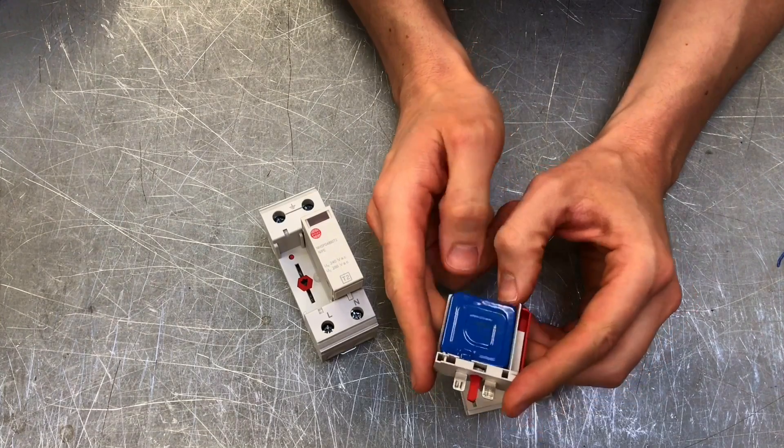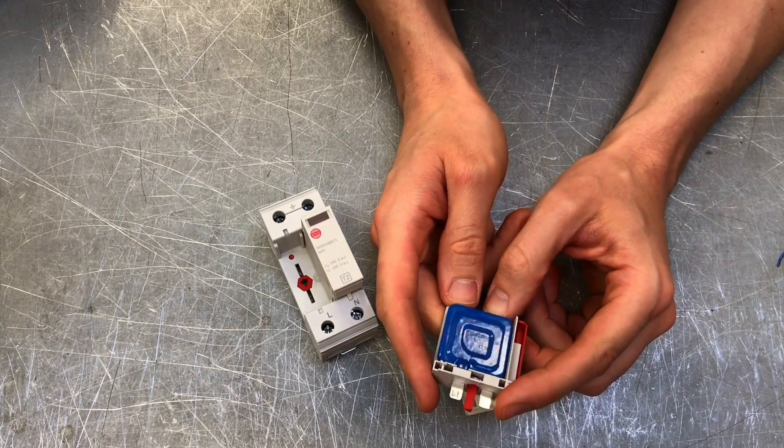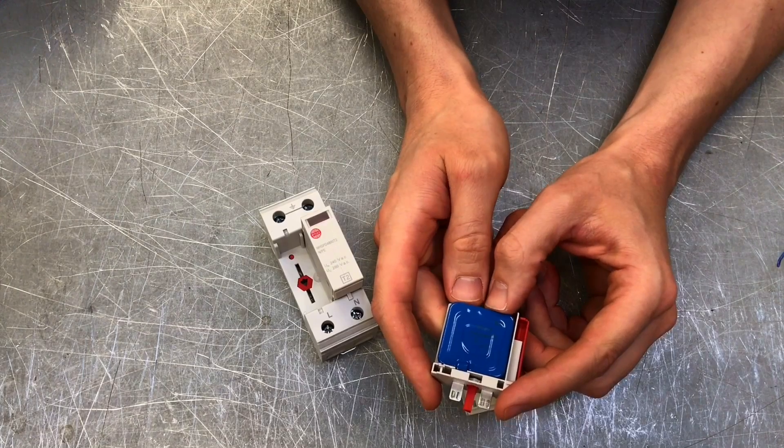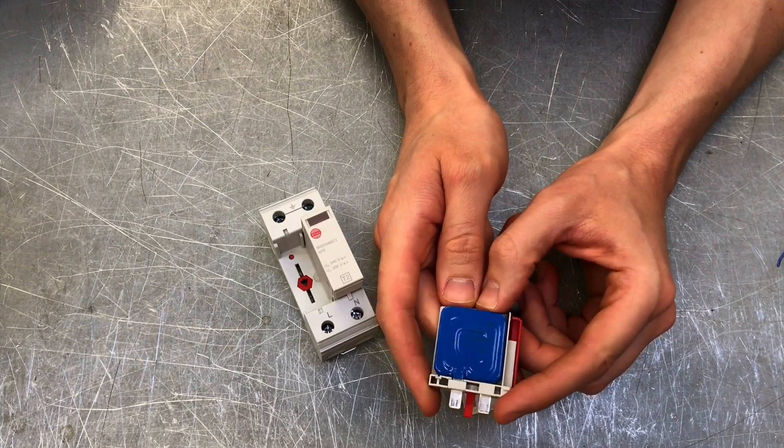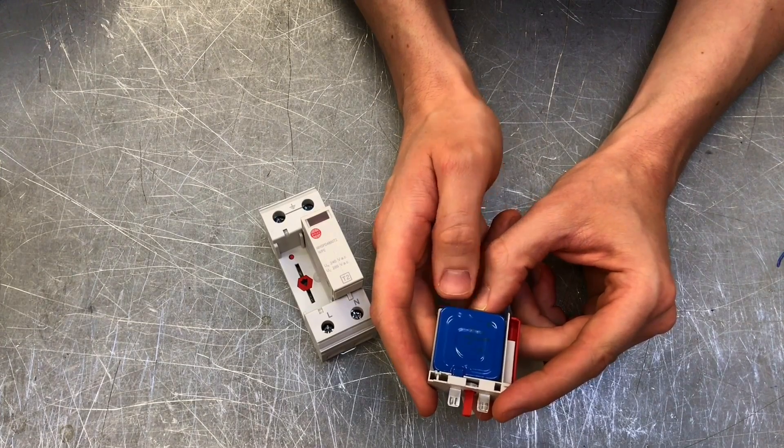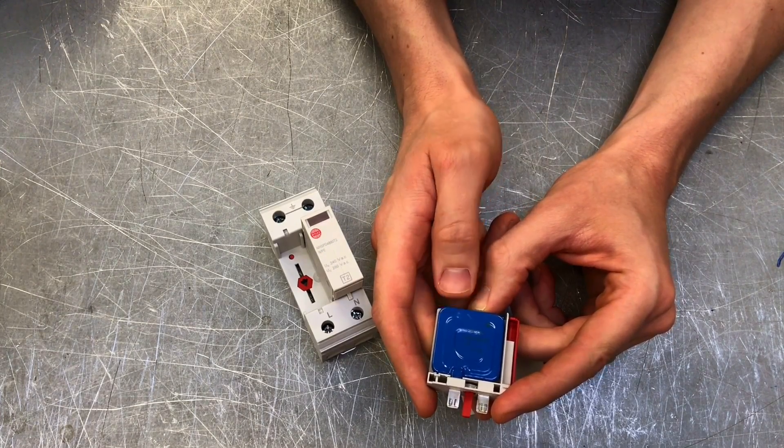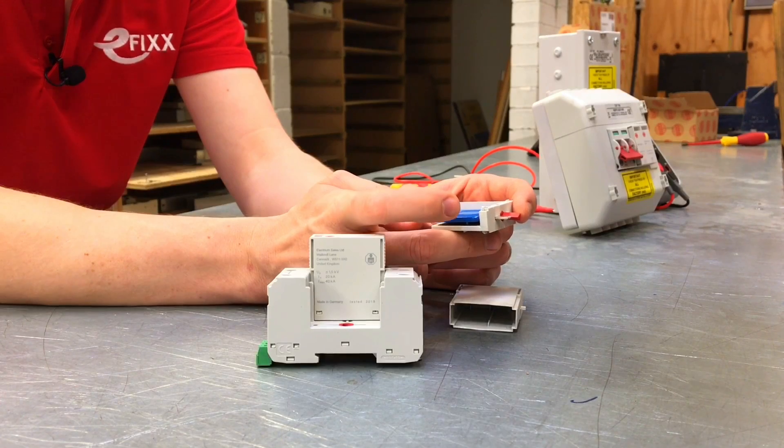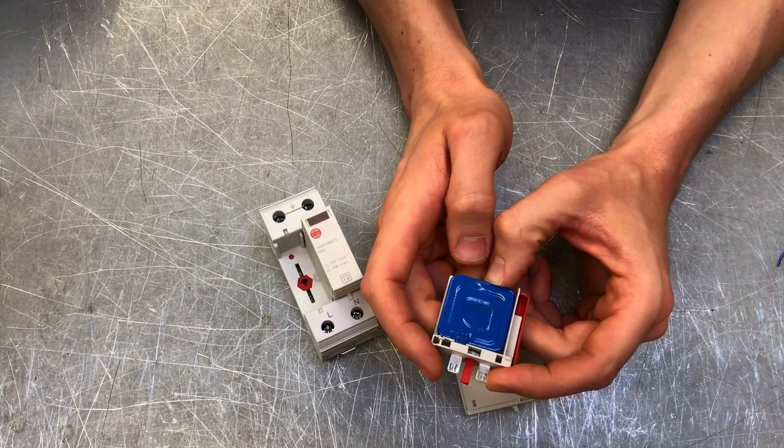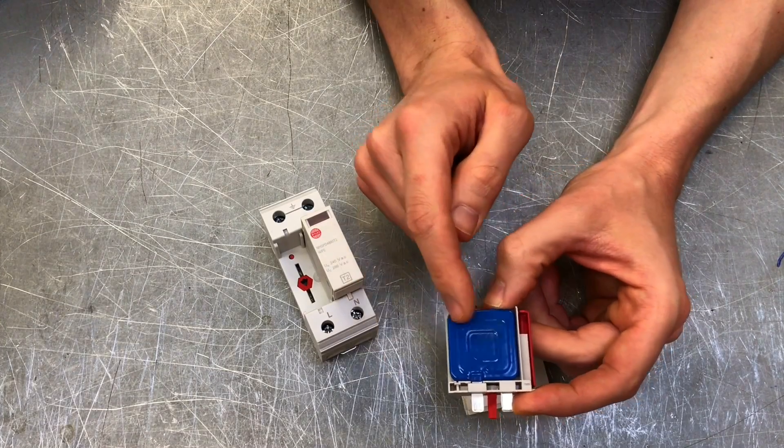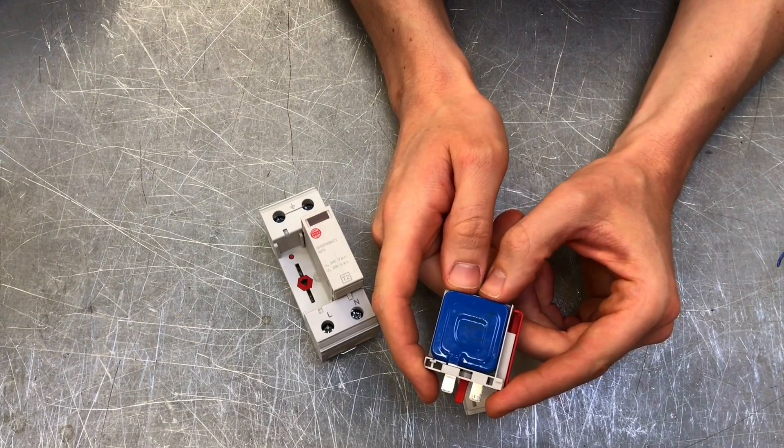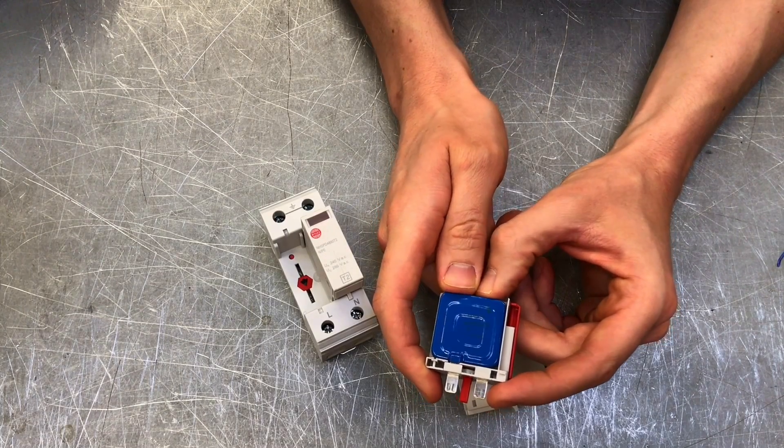This blue component is what's known as a varistor, a variable resistor. We're familiar with thermistors that change resistance based on temperature. This varistor changes its resistance based on the amount of voltage applied to it. At nominal voltage 230 volts, it has a very high resistance and won't allow current to pass through. But if we increase the voltage, this material's resistance reduces, gets very small, and current is allowed to pass through.